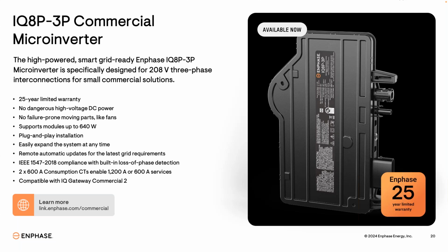Last year, we released the IQ8P3P, a new model of microinverter specifically designed for 3-phase 208 volt services. Historically, there have been limited 3-phase inverter options for small 3-phase commercial projects, and we sought to fill that gap. The IQ8P3P has all the benefits of our residential series, such as plug and play installation, the safety of no high voltage DC on the roof—which is a big deal in commercial, since there have been a significant number of fires on commercial buildings over the past 5 years or so—and also a 25-year warranty.